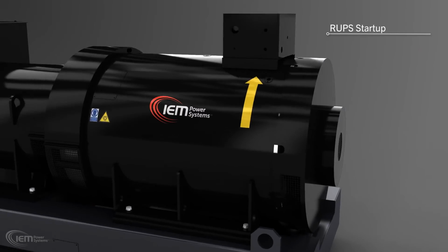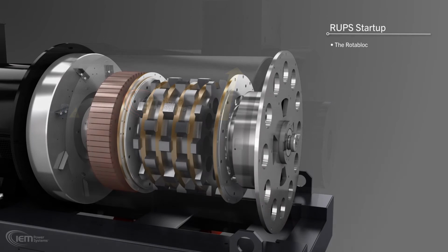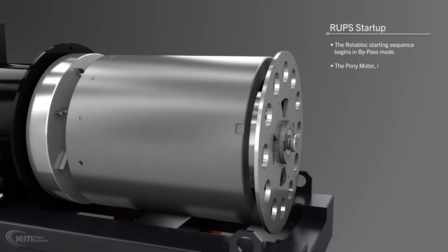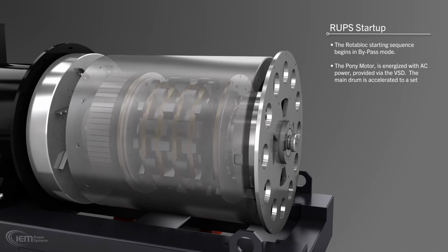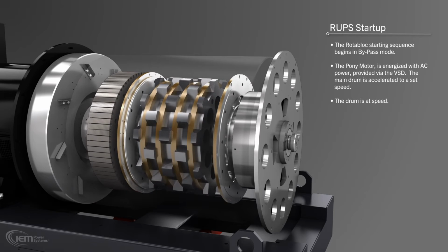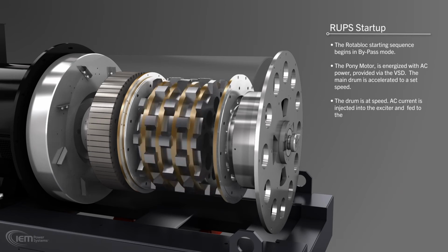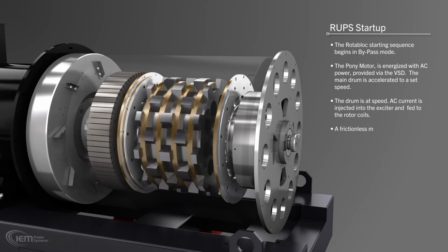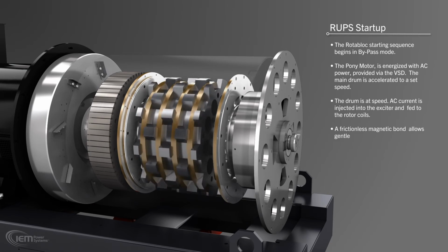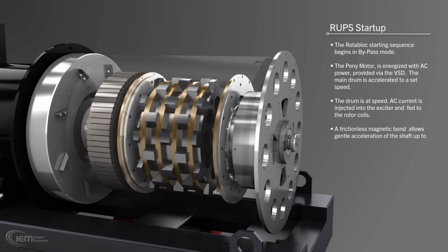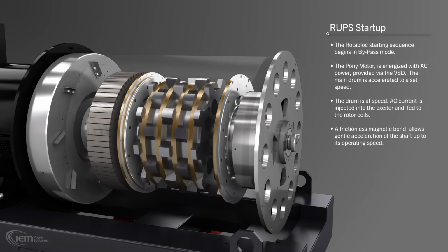RUPS startup. The Rotabloc starting sequence begins in bypass mode. The Rotabloc's pony motor is energized with AC power provided via the VSD. The main drum is accelerated to the required speed. When the drum is ready, the system injects current into the exciter, which is fed to the rotor coils. The resulting magnetic field creates a frictionless bond between the rotor and drum, gently accelerating the shaft up to its operating speed.